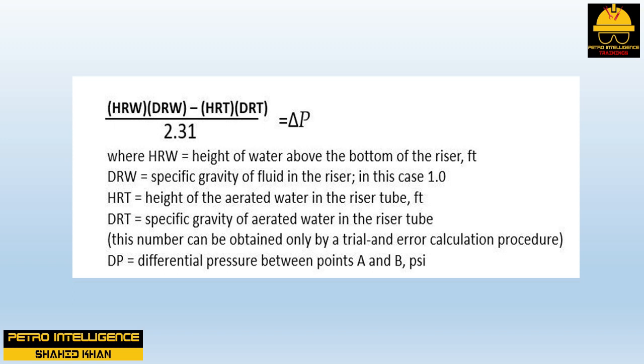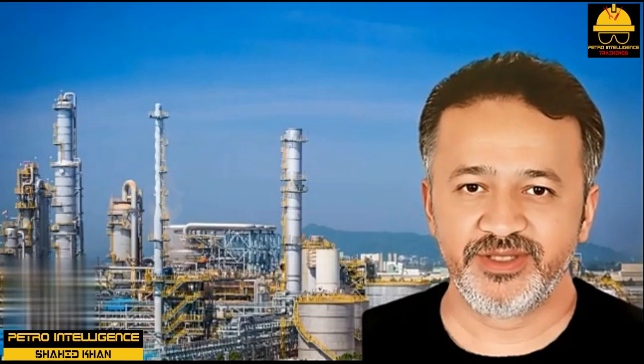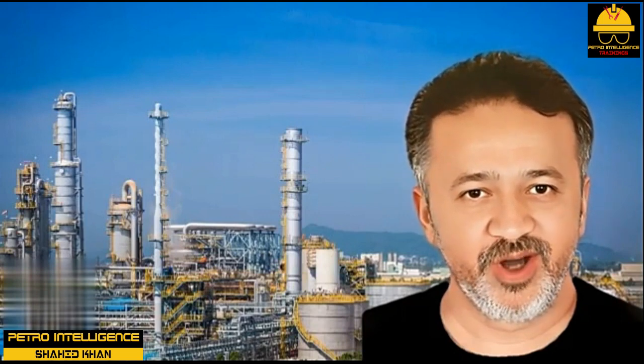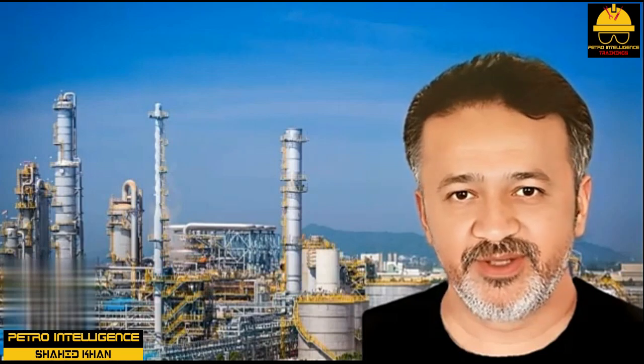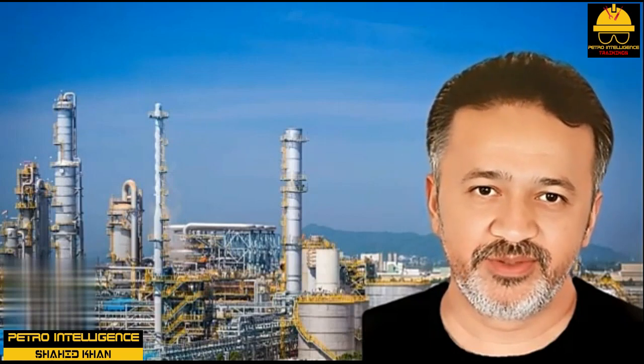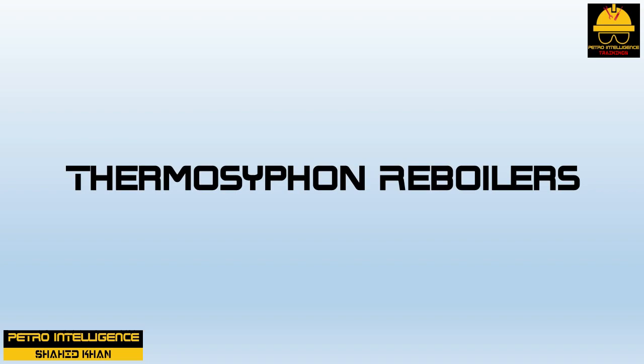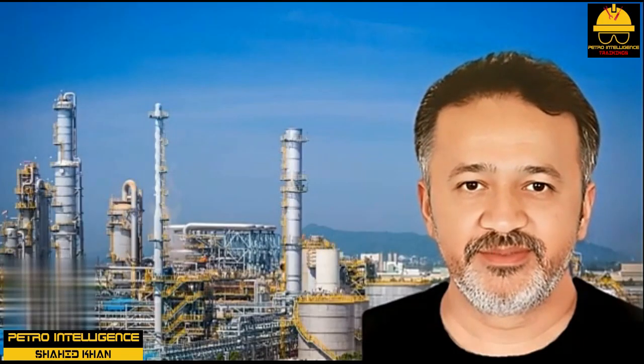In a thermosyphon or natural circulation reboiler there is no source of air. The aerated liquid is a froth or foam produced by the vaporization of the reboiler feed. Without a source of heat there can be no vaporization, and without vaporization there will be no circulation. So the source of energy that drives the circulation in a thermosyphon reboiler is the heating medium to the reboiler.